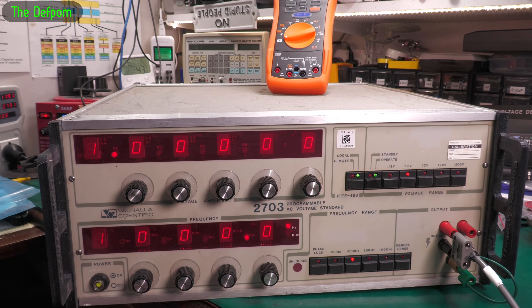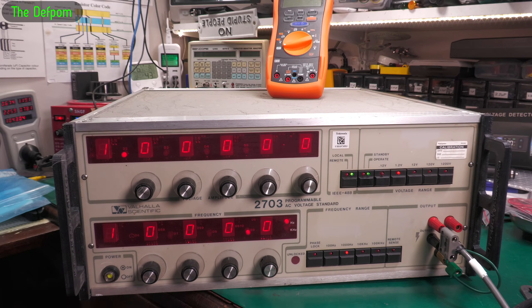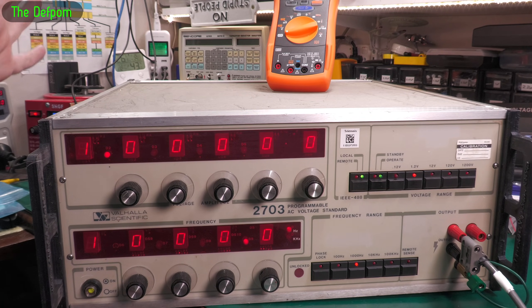I made a mistake when I was doing that. What happened is I turned the power off with the calibration key still on and it corrupted the calibration, the actual adjustment stuff, it just corrupted it all.